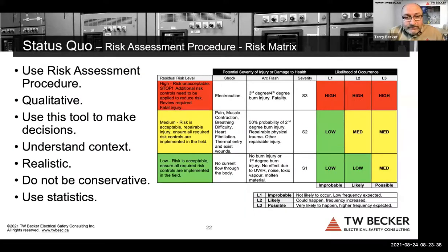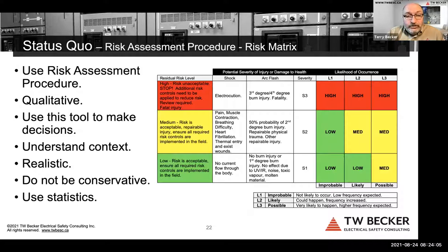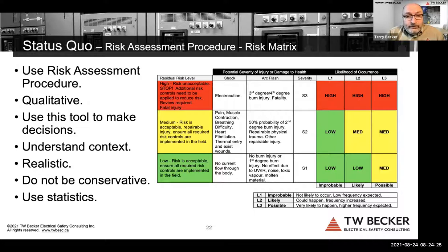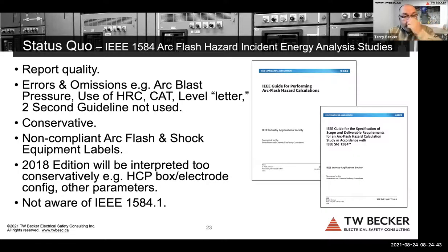Risk assessment is a powerful tool for dispelling myths and misinformation. Use qualitative risk assessment: understand the context of the work task, be realistic, do not be conservative, and use statistics, experience, and other information. I recommend work task-based risk assessments using NFPA 70E Table 130.5C or CSA Z462 Table 2, which list 31 work tasks. I use a 3x3 electrical hazard risk assessment matrix with a risk register table. A committee performs the qualitative assessment and determines residual risk level with the hierarchy of risk control methods applied.